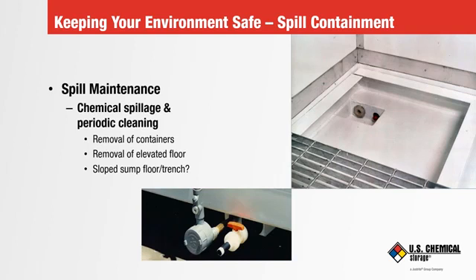And this is because the spilled chemical usually will not mix with water but will float on the surface of the rising sprinkler water. This cannot be allowed to pour over the door sills, out of the building, and into the environment. The calculated water catch will result in sump heights usually greater than 20 inches. The sump floor may be sloped.